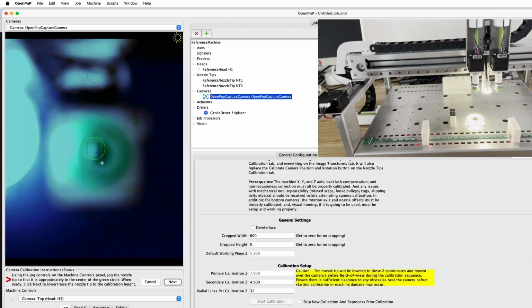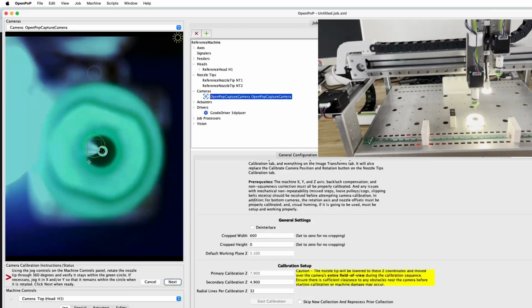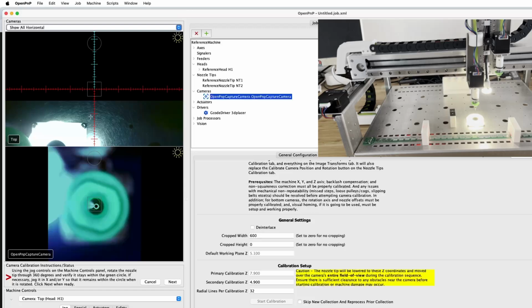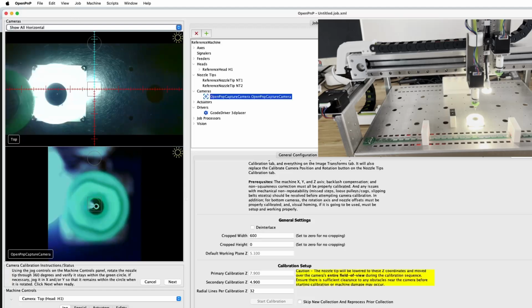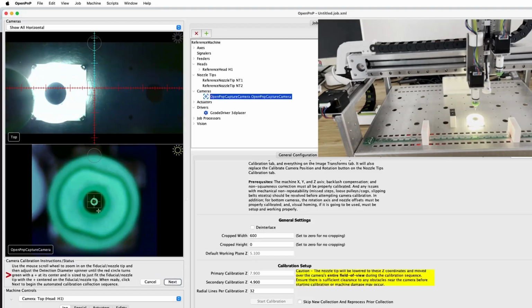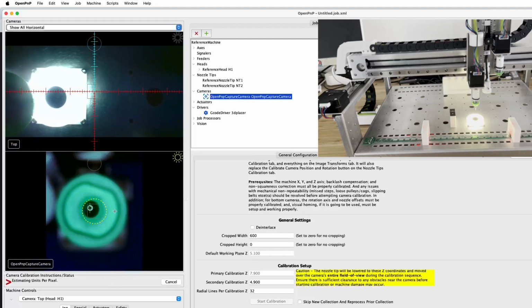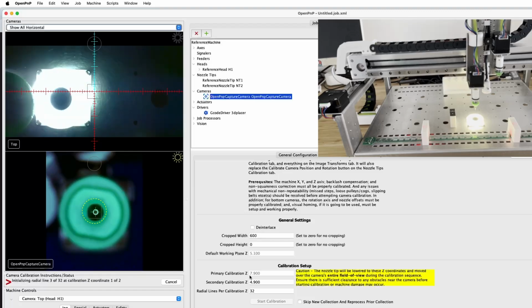So let's go, and then we just click next. So you see it actually lowers down the nozzle tips. So we just need to move. Okay, it automatically switches the camera, but we just put it to all horizontal, then we can see both cameras. So here now I just need to do this, and then you see it's already detected the size. But if the size is too small, you can make it bigger, and if it's too big, then you can adjust here. And now I just adjust like this, and then I will let it start. So the process is that it will go through this detection for this level for 7.9 millimeter high, and then afterwards it will go for 4.9 millimeters.